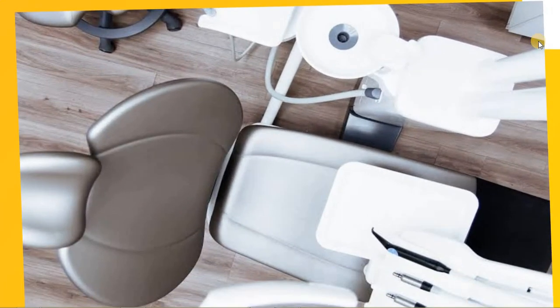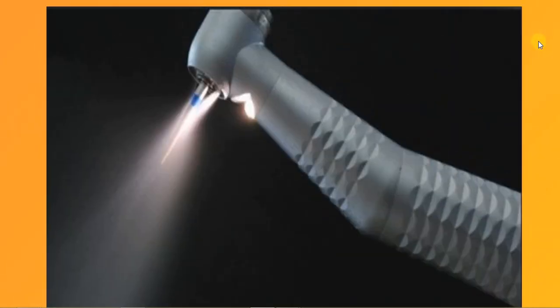It can intake saliva, blood, dentinal powder, and microorganisms from the oral cavity, contaminating the whole tubing and the treatment unit. Cross-infection can occur even if the turbine handpieces are changed for each patient.